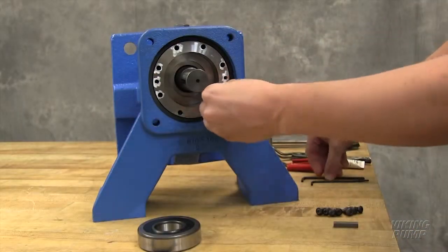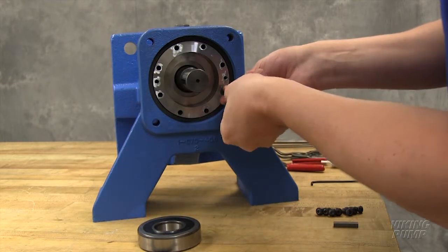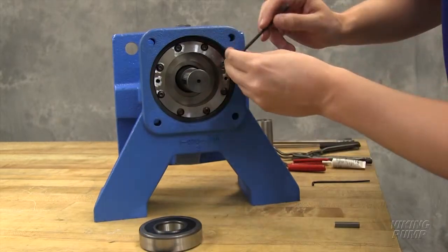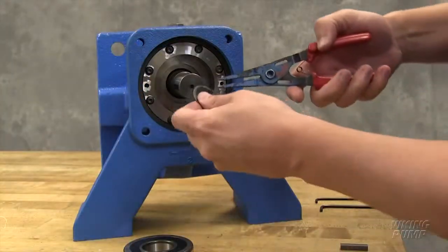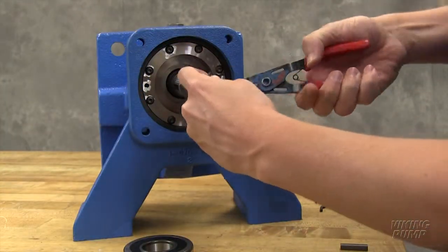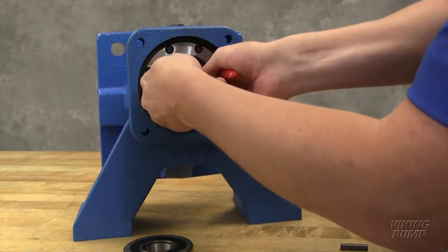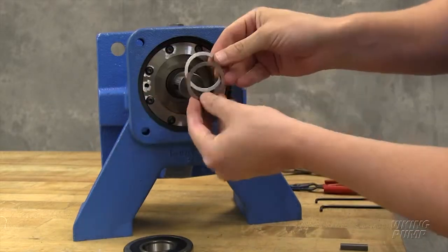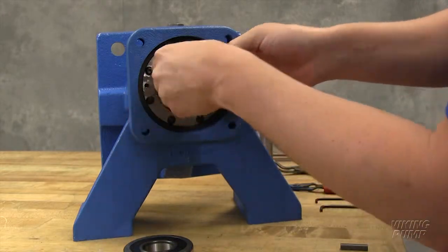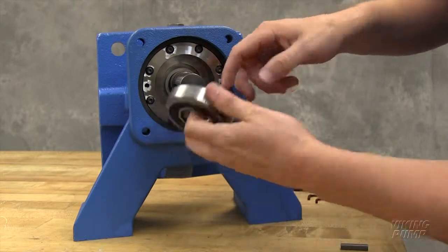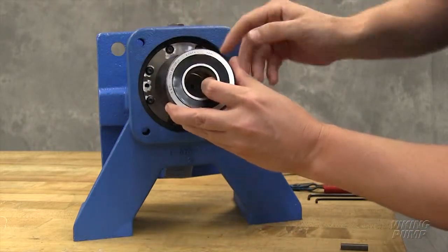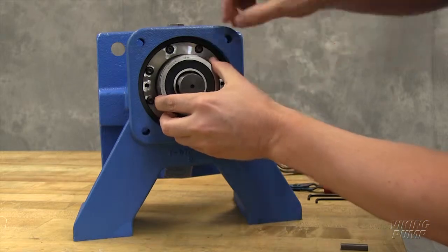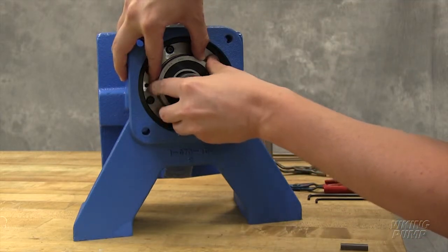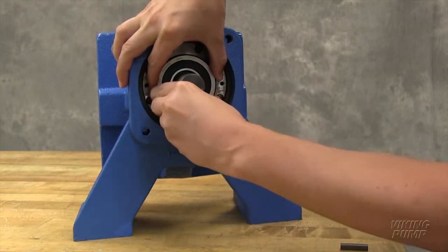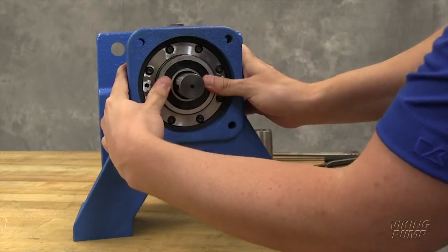Hand tighten the cap screws. These will be torqued tight after the bearing installation. Install the retaining ring into the groove in the shaft. Install the bearing shim against the retaining ring. Slide the bearing onto the shaft until it contacts the bearing shim. The bearing must be installed with the larger side of the inner race against the bearing shim. The letters on the bearing outer race will be readable when installed correctly.